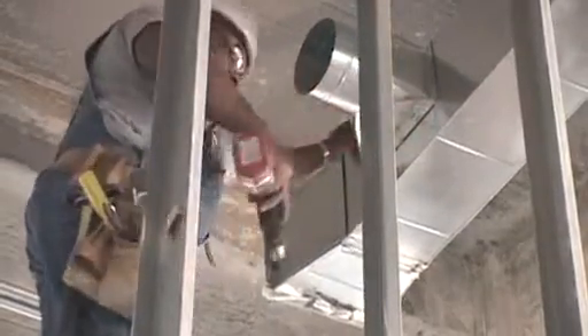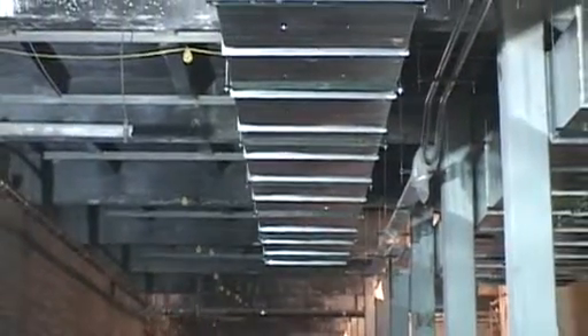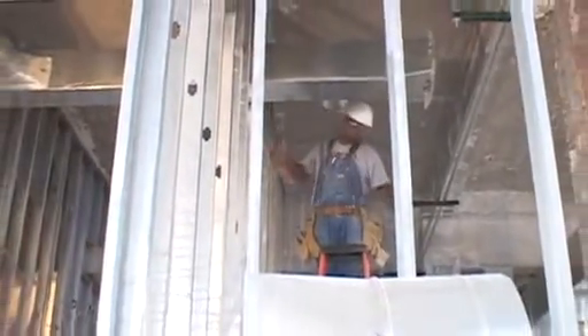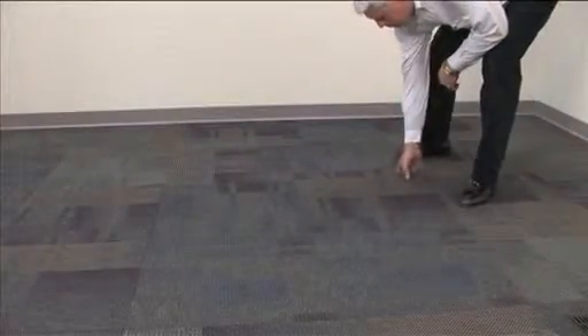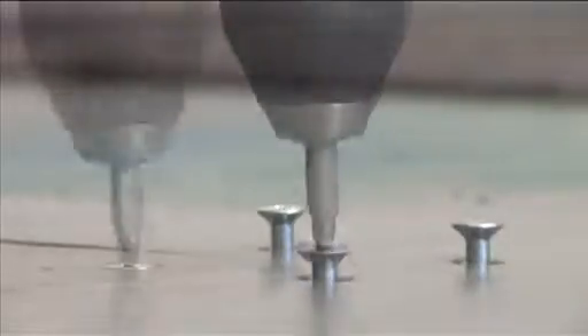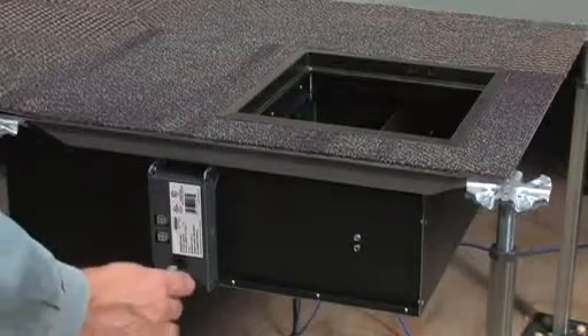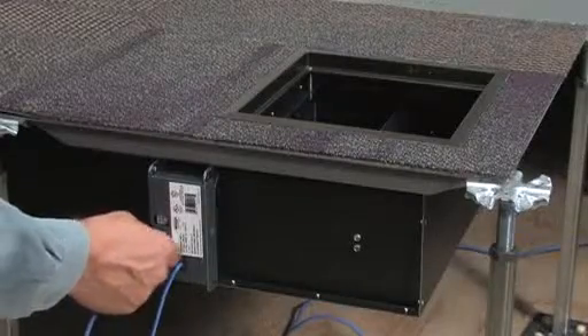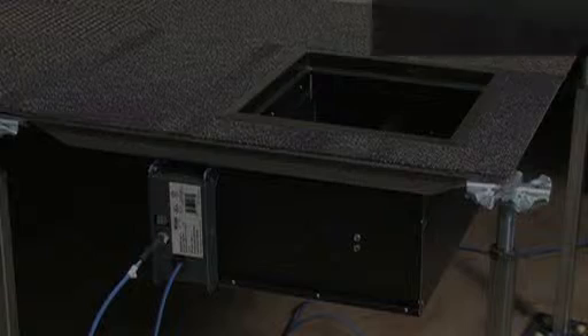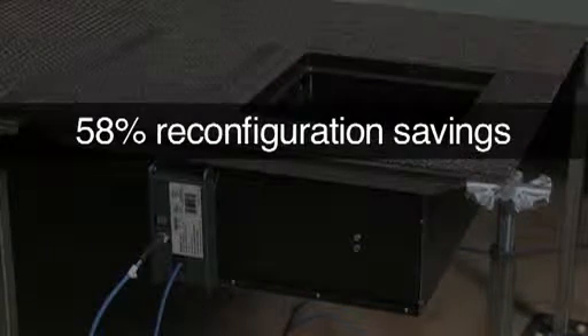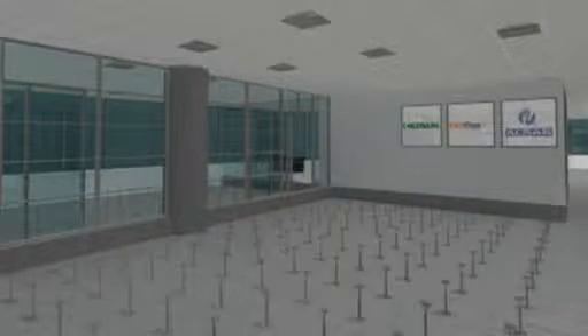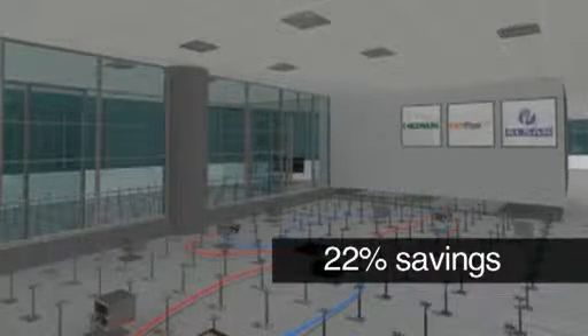Ducted overhead air often requires removing and replacing the rigid ducts, VAV terminals, and diffusers to suit reconfigured space use, which is labor intensive, not to mention the effort of doing this above a ceiling. With underfloor air distribution, the floor tiles are part of the HVAC system and are much more durable than typical ceiling tile. The swapping of floor tiles and diffusers is much easier and provides major cost-saving opportunities. Thermostatically controlled floor-mounted diffusers are daisy-chained with simple plug-and-play wiring connectors, so reconfigurations are much less complex than with ducted systems. It's estimated there can be savings of 58% over ducted reconfigurations. Furthermore, to add or change one HVAC zone, we've seen savings in the 22% range.